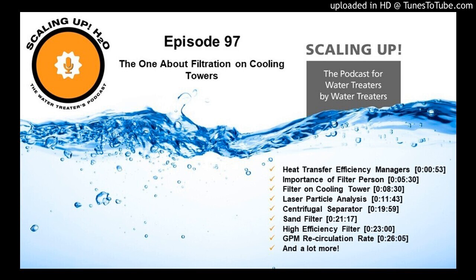Now, if you and I were working together and we were making sure that we put the right size high efficiency sand filter on a particular cooling tower, what kind of questions would you be asking me? The key is what's the GPM recirculation rate on the cooling tower? What's the total water that's going to flow through the tower? What's the GPM? And you can get that somewhat from the tonnage. If a standard cooling tower is designed for a 10-degree delta T, and it's a 500-ton chiller, then the design condenser water recirculation rate is 3 times the tonnage, which is like 1,500 GPM.